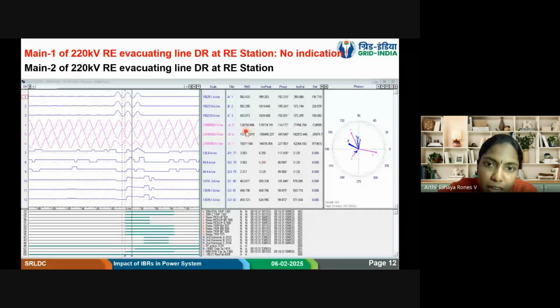The directional earth fault protection, as I said, is a very sensitive protection. The pickup of these protection schemes is very low. Typical pickup at primary will be 200 ampere. So when the pickup is 200, if the current is going to 600 and so on, obviously it will get picked up. However, 200 pickup will not operate immediately because it will have some IDMT characteristics, and as per that, it will operate. But if we have enabled high set without any delay, then it is prone to maloperation. So in this case, it had maloperated.